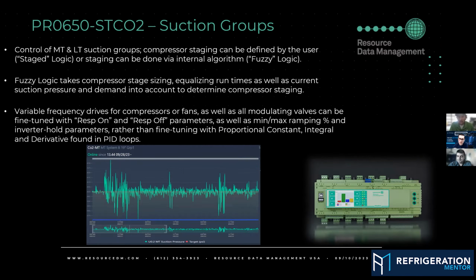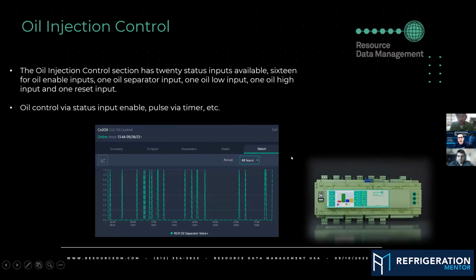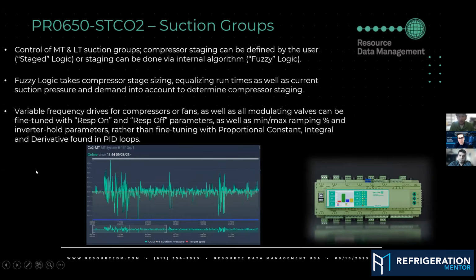The thing is, I hear this a lot: "Oh, I need to go in and fine tune the PID." How often, after a store is set up and the control guys have set it up, should technicians be touching a PID? Cody. No. Now you get a manager in there, or what I call a high technician, who knows what they're doing and is read up on it.